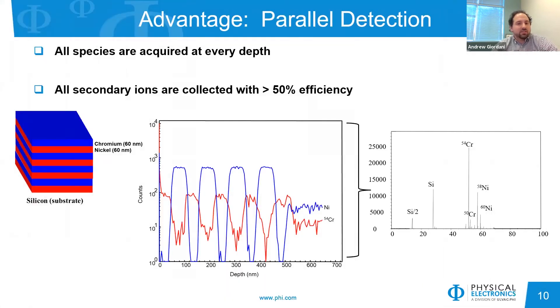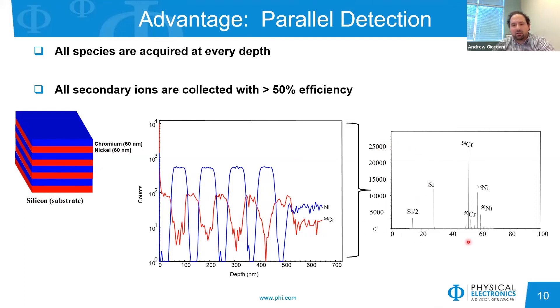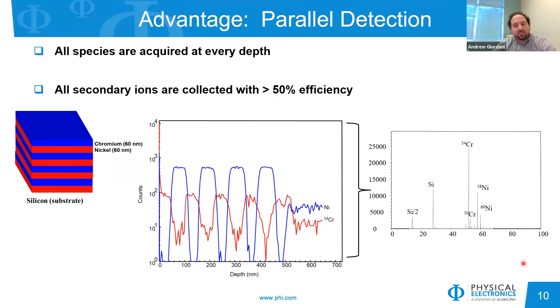Parallel detection means all species are acquired at every depth. Looking at this chrome-nickel alternating film stack depth profile, you can see the chrome and nickel alternating signals, but you're also getting all species coming off — all isotopes and silicon species from the substrate. You can reprocess the data on the back end to create your depth profile. All secondaries are collected with greater than 50% efficiency, providing good transmission.